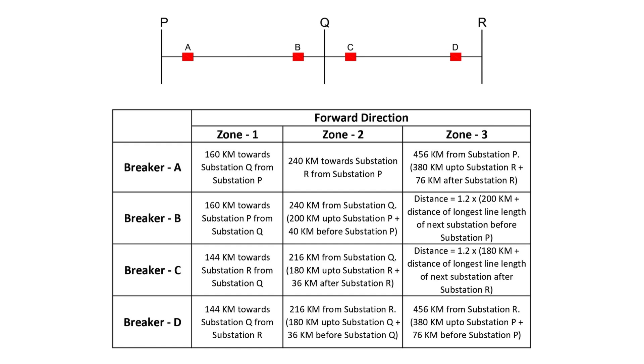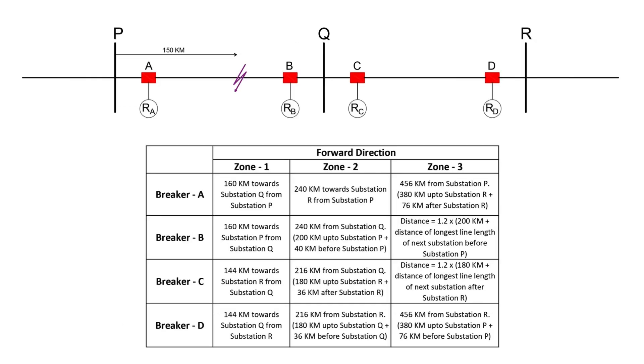Consider a fault at 150 kilometers from substation P along the PQ line. Both relay A at substation P and relay B at substation Q will detect this fault within their zone 1 range. Since this is a zone 1 fault, both relays will send instantaneous trip commands to their respective breakers.